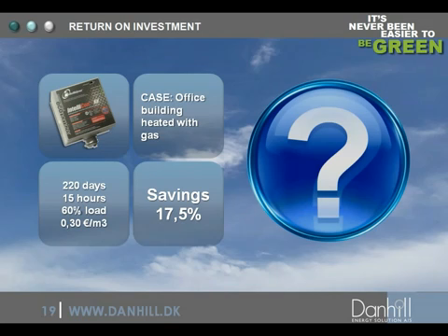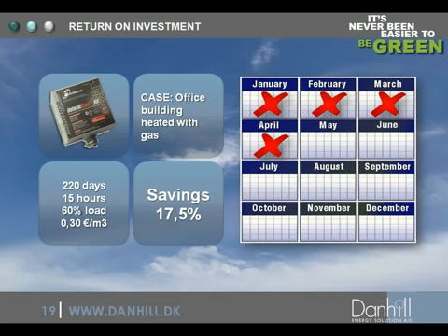To give you an indication of the payback time, I have prepared this case for you. We are looking at a large office building heated with natural gas from a single boiler with a 720 kilowatt rating. Assumptions are a heating period of 220 days a year, 15 hours per day at a 60% load. With a gas price of 30 cents per cubic meter and our average savings at 17.5%, the payback time will be 4 months.